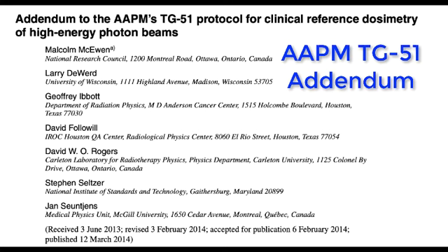One thing you should be aware of is that there was an addendum published to TG51 in 2014. Here's the link for that. It didn't completely replace the protocol, it just made some minor tweaks and added some data for different ionization chambers based on Monte Carlo calculations, but you should be aware of this update.